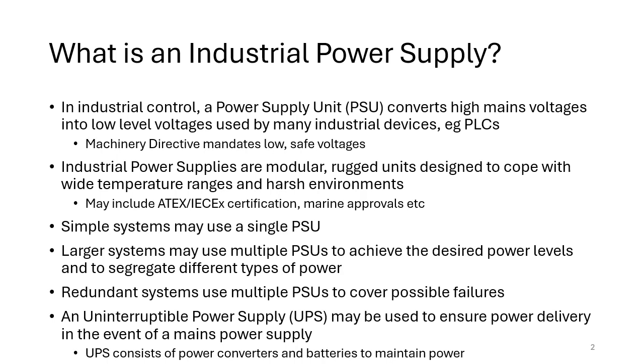For example, you might have two power supplies in parallel, and if either power supply fails, the other one can take over. I'm not going to talk about this too much, but we also might have an uninterruptible power supply, or UPS. This can be used to ensure power delivery in the event of a mains power supply failure. It's a device that consists of power converters and batteries. The idea is we take the mains voltage, convert it into DC and charge up batteries. Then if the mains input fails, we take the output from the batteries and convert it into AC, or possibly keep it as DC, and it's used to provide power to the control system until the AC mains recovers.